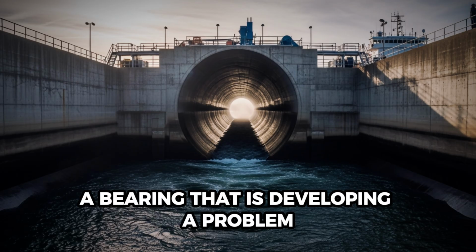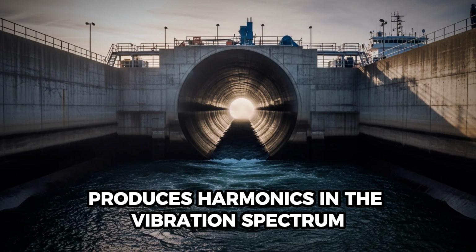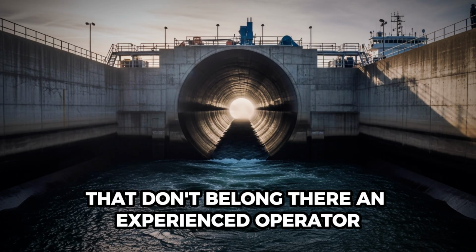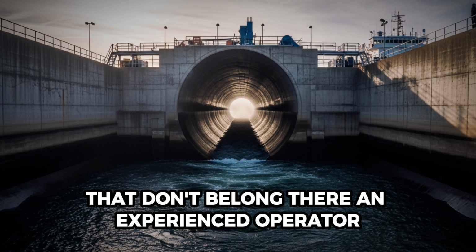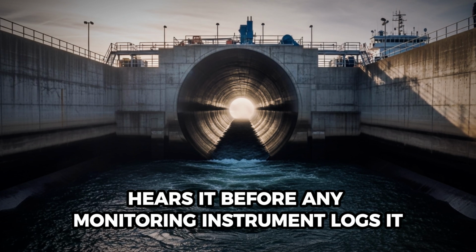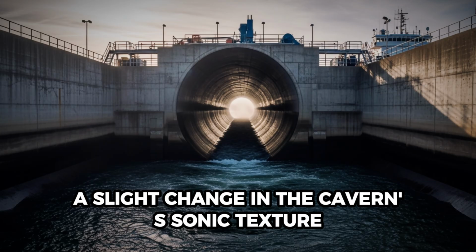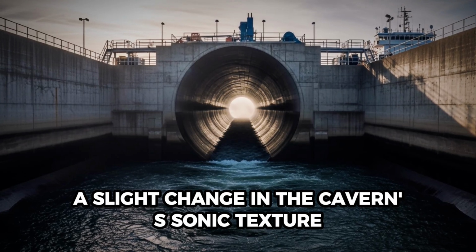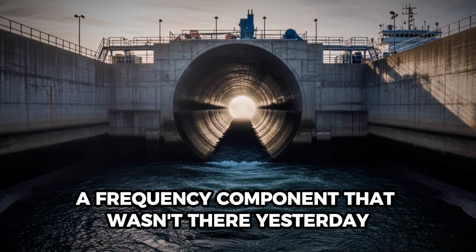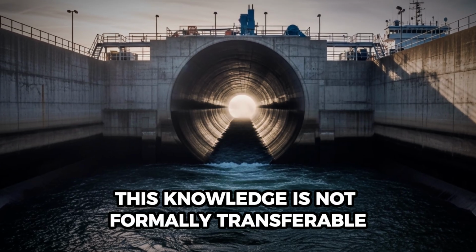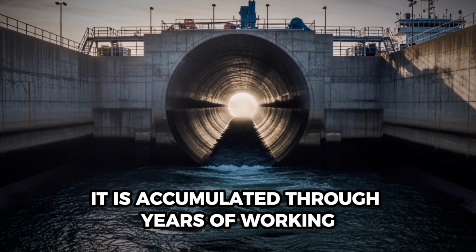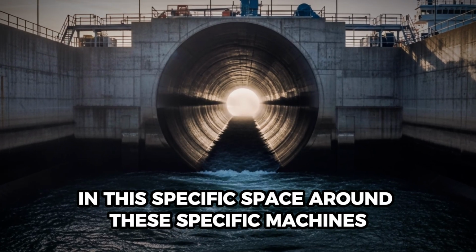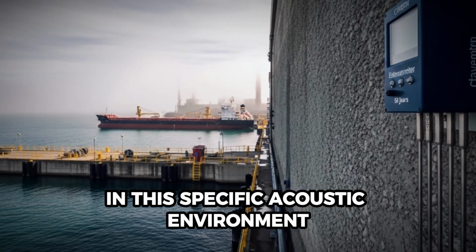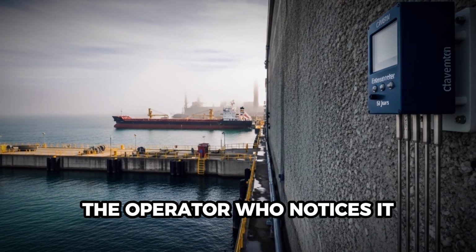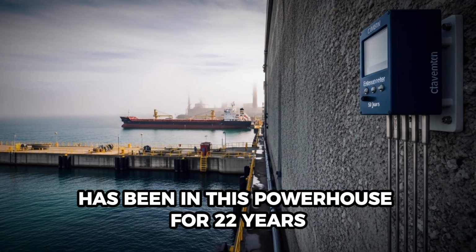A bearing that is developing a problem produces harmonics in the vibration spectrum that don't belong there. An experienced operator walking the generator gallery hears it before any monitoring instrument logs it. A slight change in the cavern's sonic texture, a frequency component that wasn't there yesterday. This knowledge is not formally transferable. It is accumulated through years of working in this specific space, around these specific machines, in this specific acoustic environment. The operator who notices it has been in this powerhouse for 22 years.